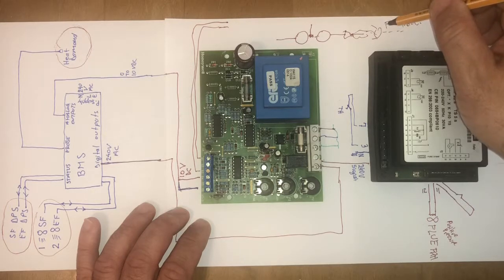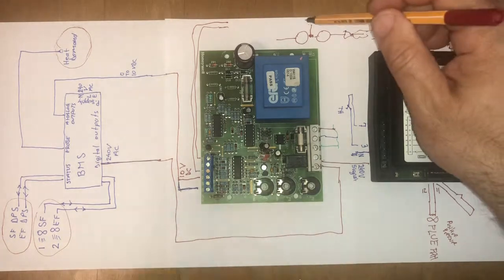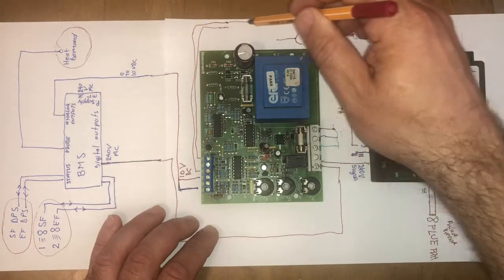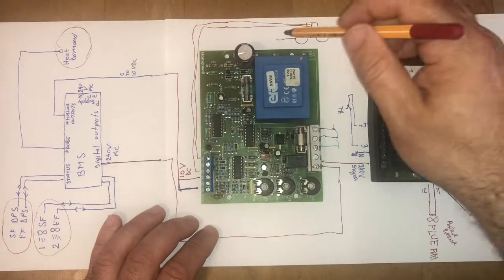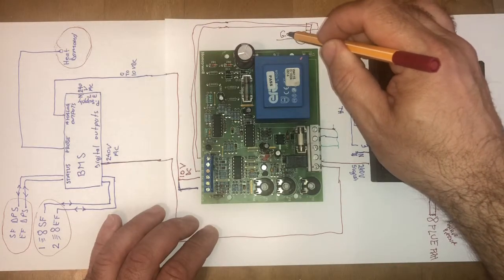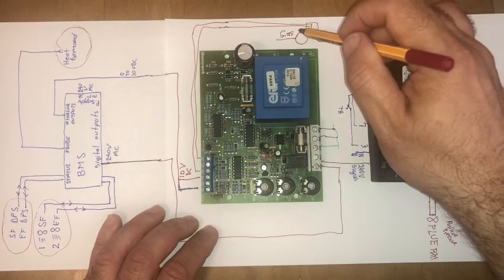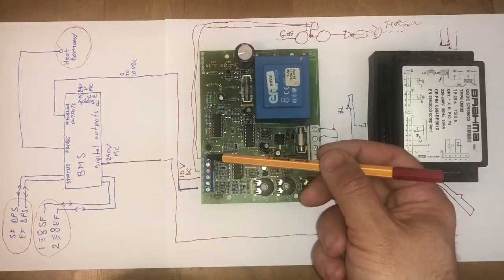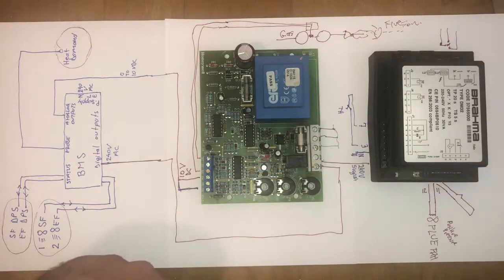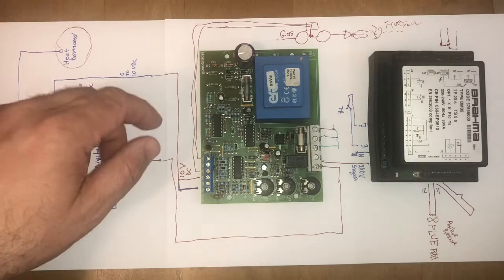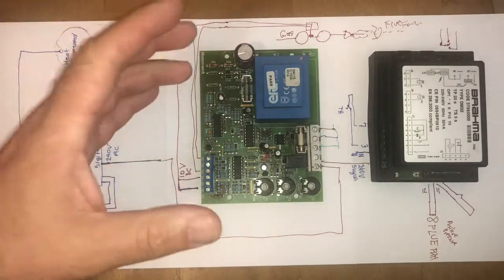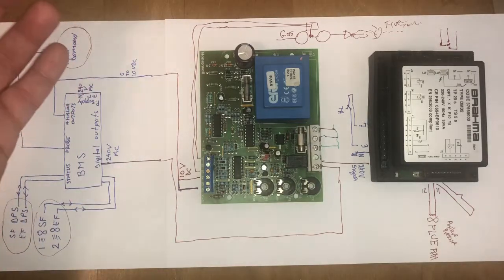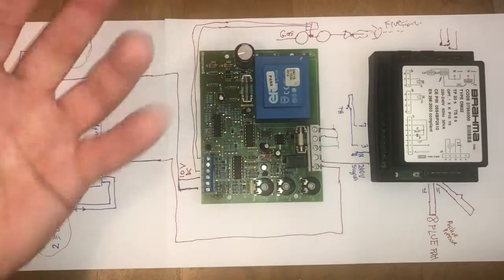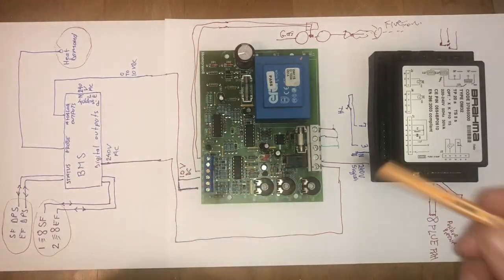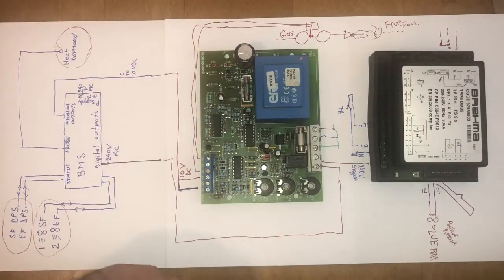Now, this actuator, it's controlled. This is the gas. So this actuator of the gas valve, and I'll show you in a minute how the gas valve looks like. It is controlled by the first three connectors, as you'll see here. It's 61, 62, and 63. And for a couple of seconds, when the flame comes on, the flame comes very strongly, and then it lowers itself, because this controller controls the high flame, low flame.